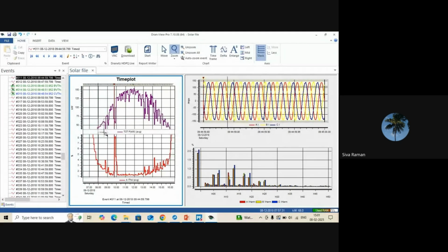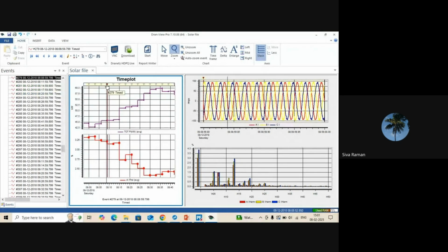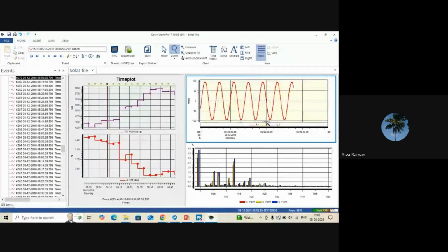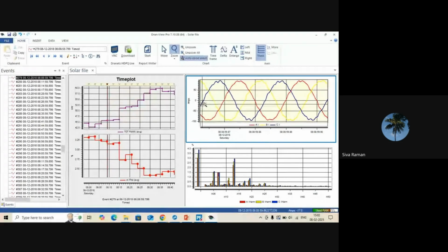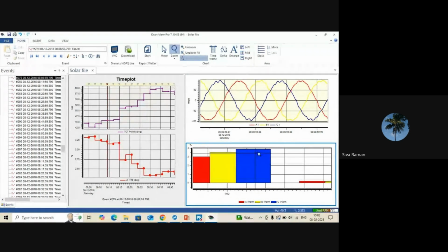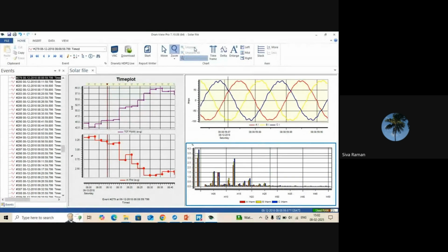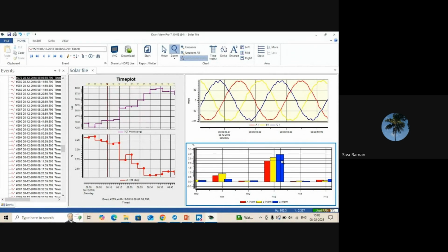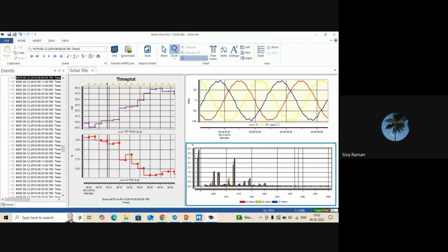Then I will go to this location where a lesser amount of power is delivered. At this point, it is delivering only 45 kilowatt. For that period, you can see the current harmonic distortion. We can observe a good amount of harmonic distortion in the current waveform, and the distortion has increased. Earlier, when it was delivering 123 kilowatt, it was 2% THD. Now it is almost 4% THD. The 13th order is contributing almost 3%.